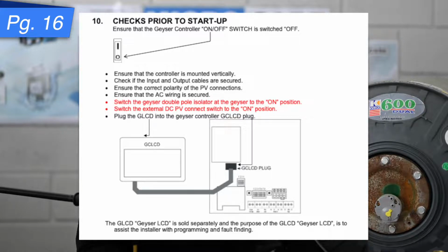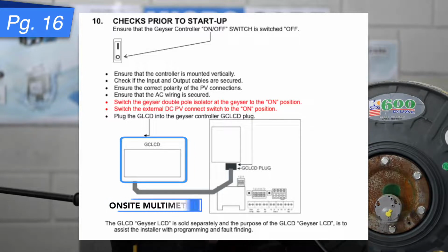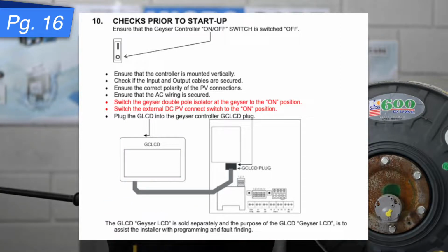Now, we've got a unit called the GC LCD. You see it listed here in the middle of page 16. This is sort of like an on-site multimeter. Installers, we request that they have one and keep it with them. This is not something to leave on site, and it's something that you plug in. It's a ribbon cable connection, and you'll see there on the controller where it gets plugged in on the page. Now that is to give you an indication of what's actually happening on the controller. So it's a nice little helpful tool. It's really affordable, and we recommend that if you're installing geyser controllers, that you have your own GC LCD and you keep it with you.